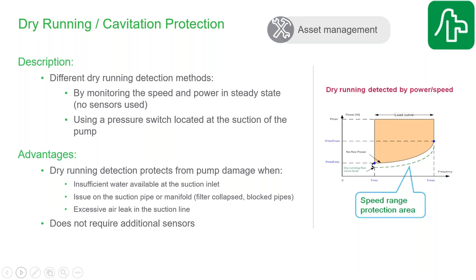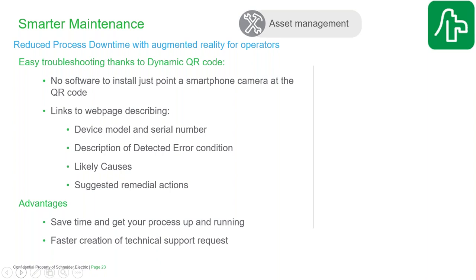So the drive can in fact detect this even without having any pressure sensors or upstream sensors at all, just by the drive looking at how much energy it takes to turn the shaft of the motor compared to what it expects it to take. And if less energy is required, it means you've got less mass inside the pump chamber, which means you have less water available. The drive can react, protect the pump, shut it down and call for operator assistance if that's occurring, to protect your assets and avoid equipment damage.